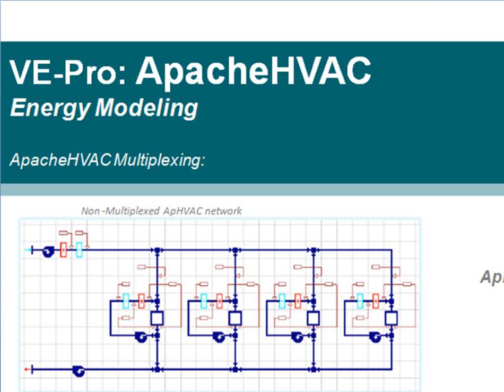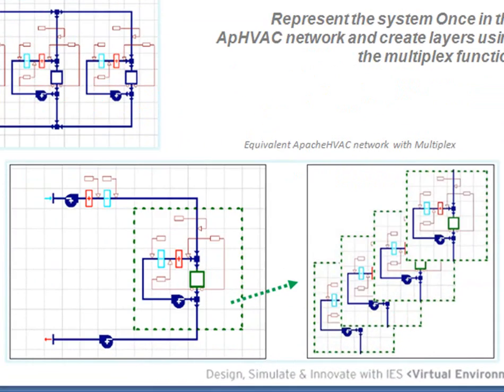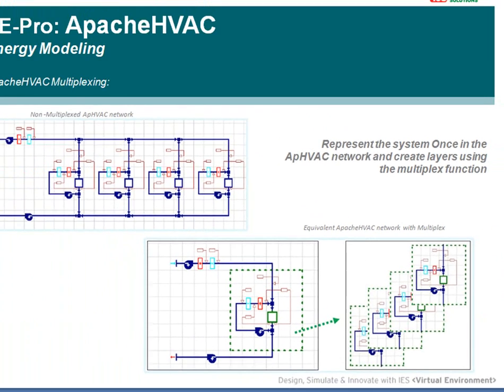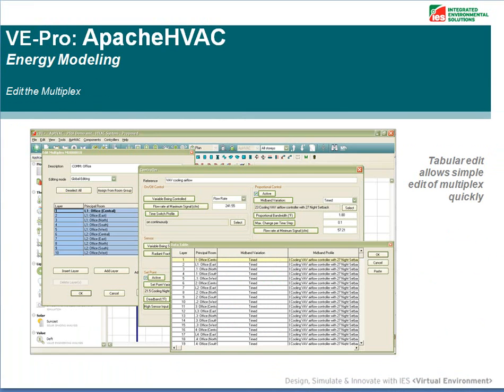This leads to very large networks that are a nightmare to edit. With the multiplexing feature, this is all avoided. Looking at the bottom image of the slide, you can represent the common outside air system and create one fan coil unit representation in the network. This fan coil unit can then be multiplexed, with the system layered so that there are multiple layers — four in this case — representing each of the four zones and systems. You can easily edit the inputs for the layers in your multiplex using the tabular edit function, which allows you to select multiple layers and variables to edit at one time. You can also copy and paste the inputs directly from Excel.